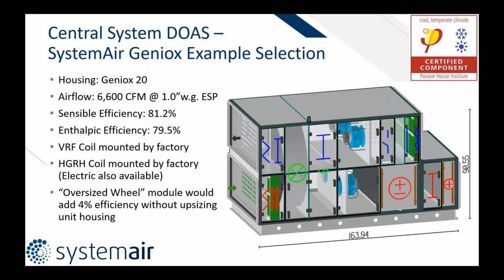Here we have a housing size Geniox 20, with an airflow of 6,600 CFM at an inch of static pressure. The sensible efficiency, and note that this is not with an oversized wheel, from this wheel was 81.2%, and enthalpic efficiency was 79.5%. The VRF coil was mounted by the factory, and so was the hot gas reheat. So know that we could also do hot water reheat or electric reheat. And if I were to make that an oversized wheel, I would have added 4% without upsizing the actual unit. So you do pay for the upsized wheel and wheel module itself, but that pales in comparison to the price of upsizing the whole unit, which you would not have to do.